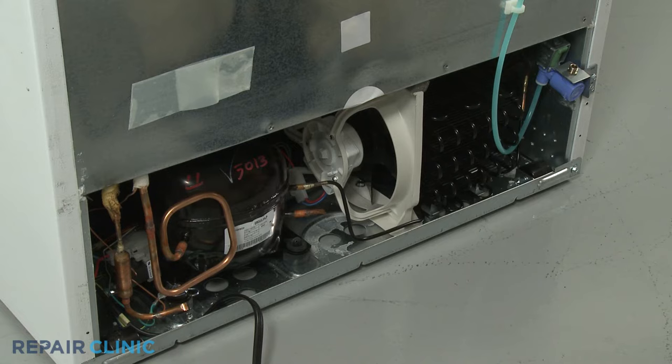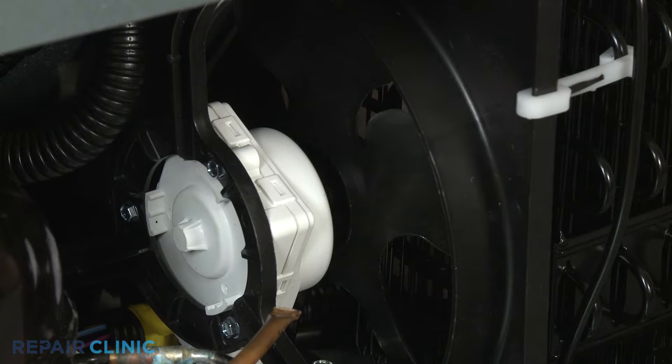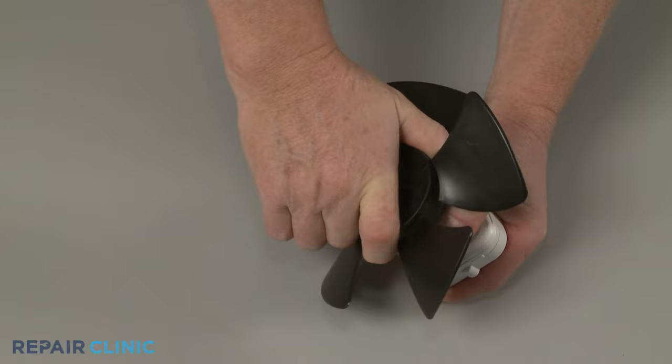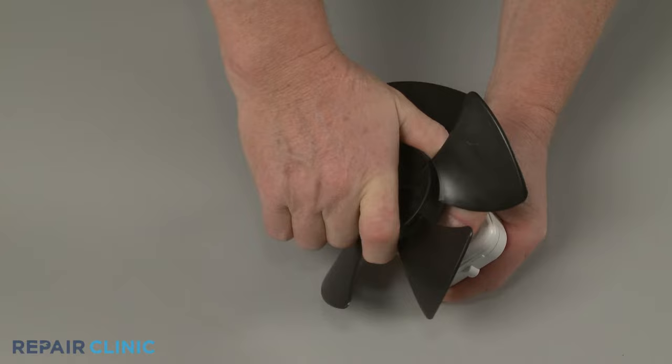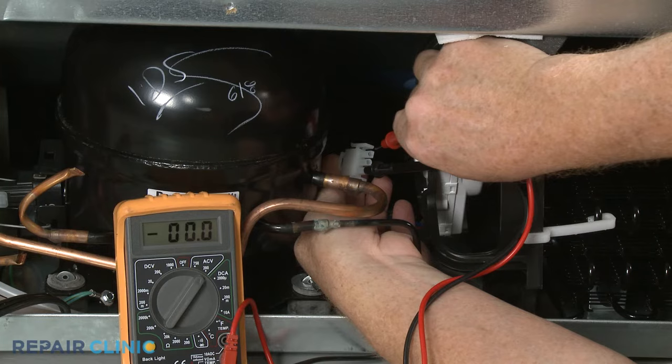You should check to see if there are any obstructions preventing the fan blades from turning. If the blades do not spin freely, it's likely that the motor bearings are worn out. You can also use a multimeter to confirm the motor is receiving the appropriate voltage, as indicated on the motor. If the motor is receiving proper voltage but does not run, then the component is defective.